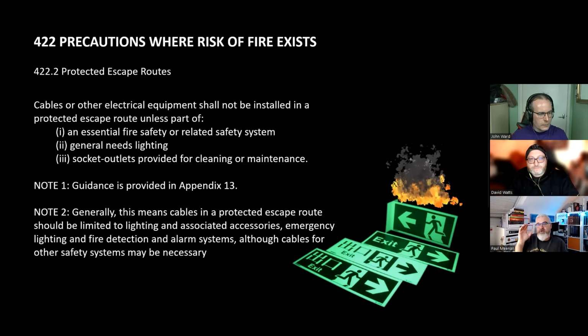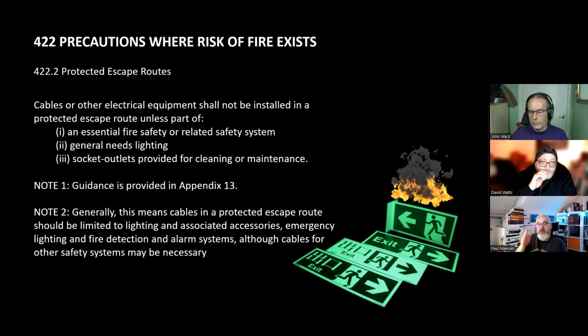This is guidance. If you work on, let's say, a 10-story tower block and everything's wired in, I don't know, 25 mil armoreds from a riser board all the way through a corridor, as long as you've got fire rated fixings, you're not fully compliant with the intent of this, but you do have a level of compliance. It's about planning the next phase for when you do your next rewire. Am I going to be using fire rated armoreds? Yes, of course, because there's been changes to regulations. It doesn't mean you go and rip everything out.